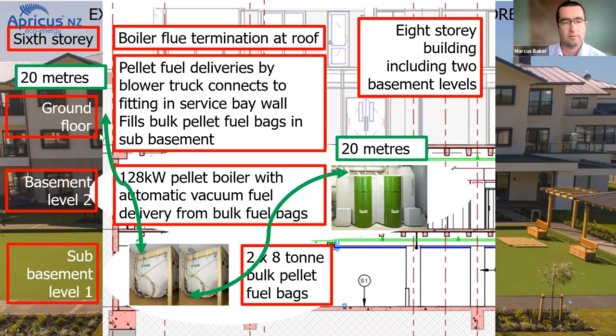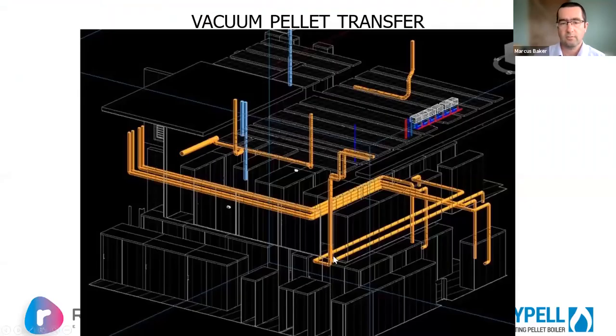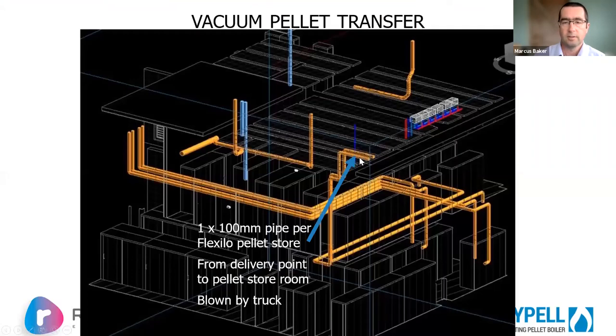And then another 20 meters this direction goes up to the delivery point. And so NDY's beautiful little model shows it quite nicely. We've got a 100 mil pipe that is essentially going to street level, so the bin and laundry delivery bay, and that will obviously all be fixed, and a nice little box in the wall that's tidy and hidden away. And it will also have an indicator so that when the Flexilos are full, a little light comes on here to say, stop delivering, or not full.